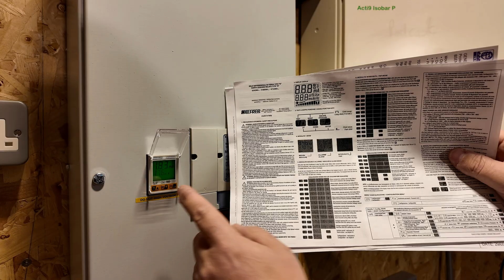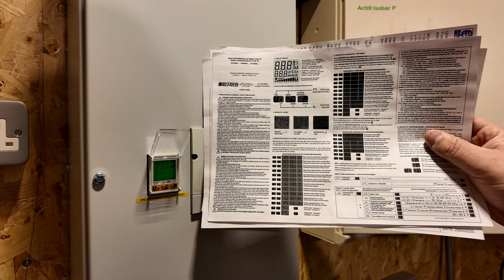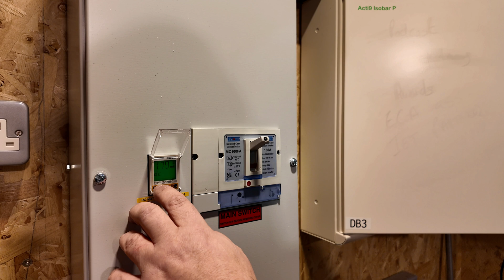So if you don't want to watch the YouTube video, you want to pop your glasses on because this is incredibly small writing, it'll take you through how you can program this up and set it up in the way you want. We'll just demonstrate the test, and this will go with a clunk and probably scare me, but if we hold the test button down, you can see there it's tripped and it's illuminated red. So we now need to hold the reset button down. Now that's gone back green, we'll be able to cycle that to the off position and then turn that back on. So that's tested the function and operation of the RCD there.